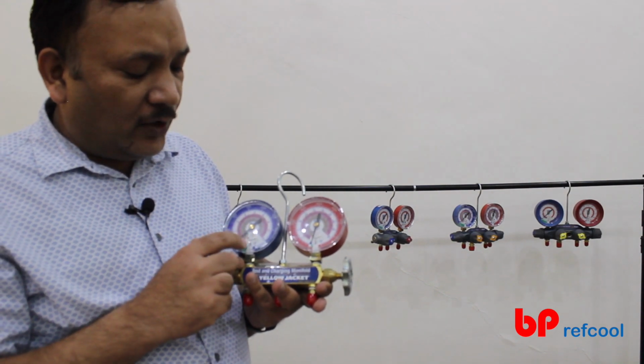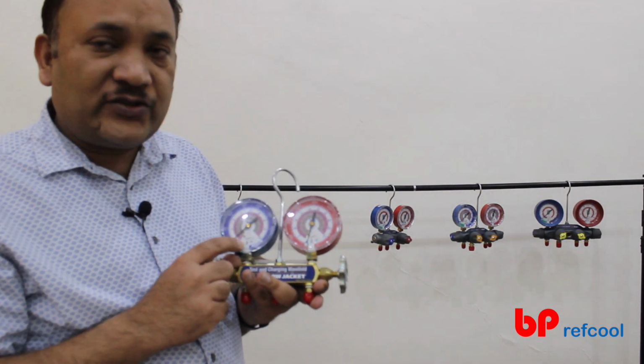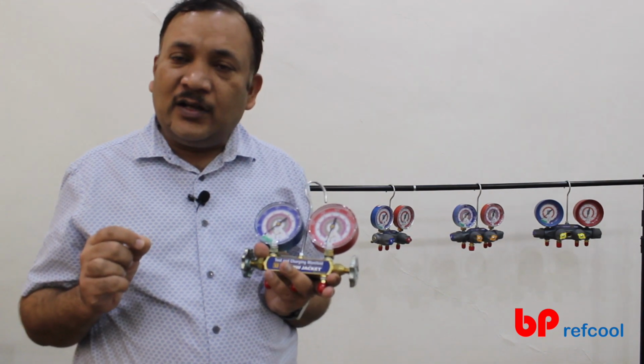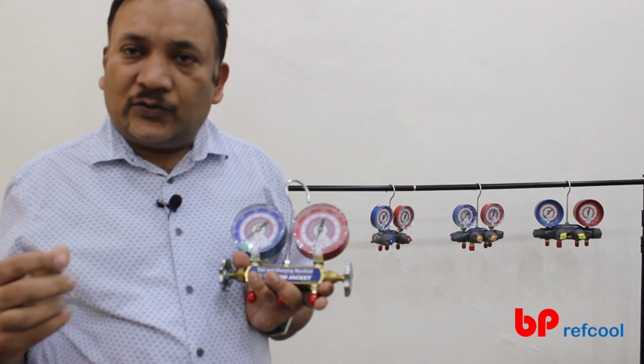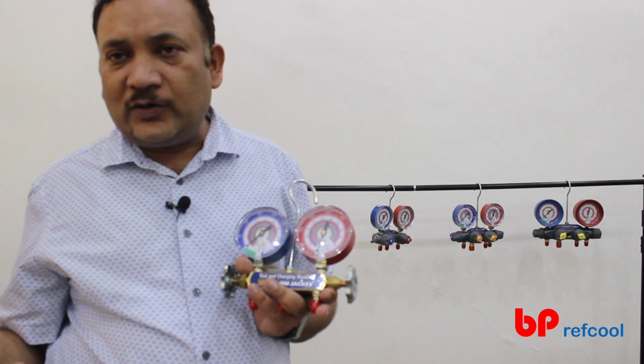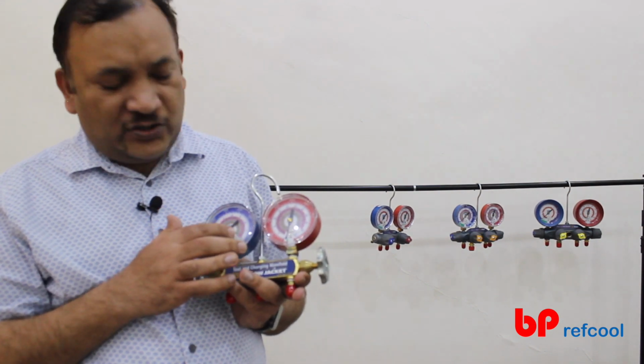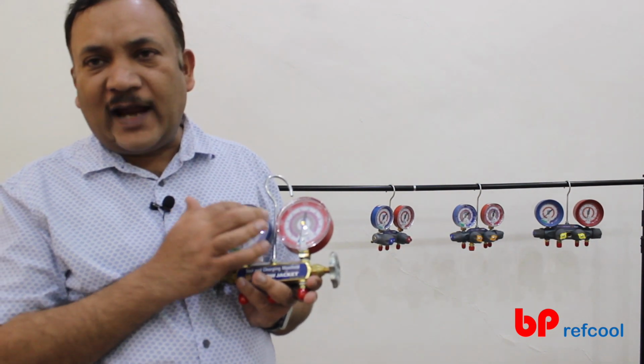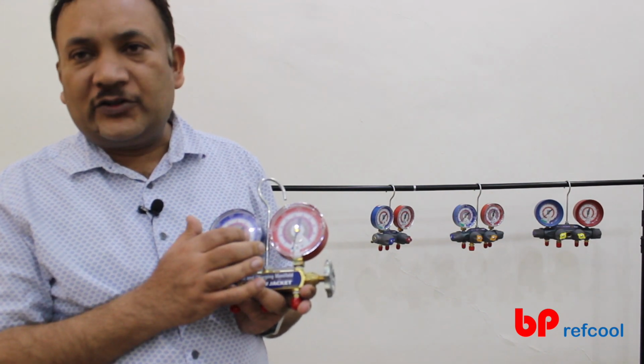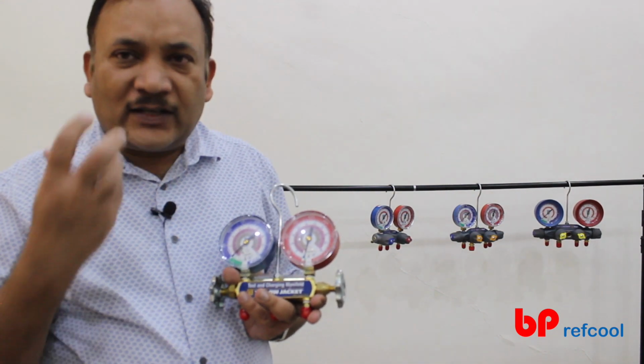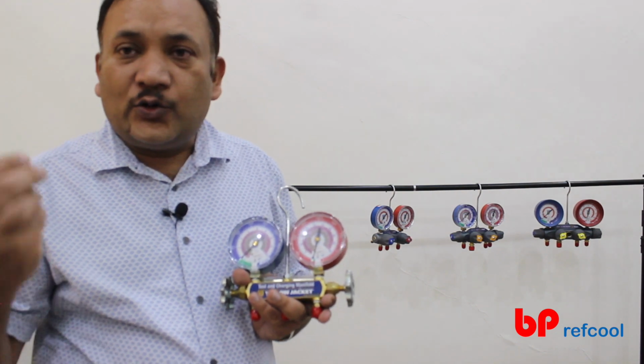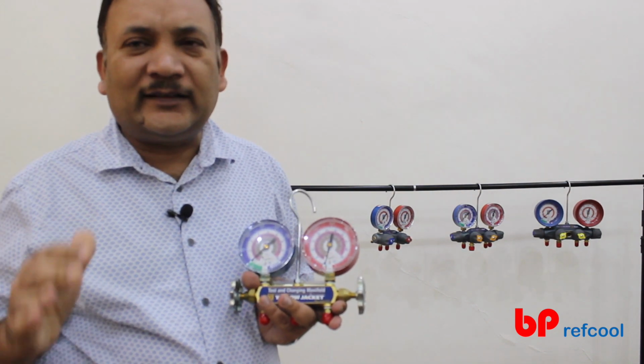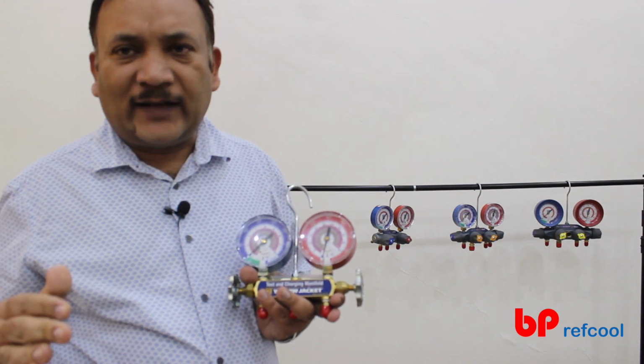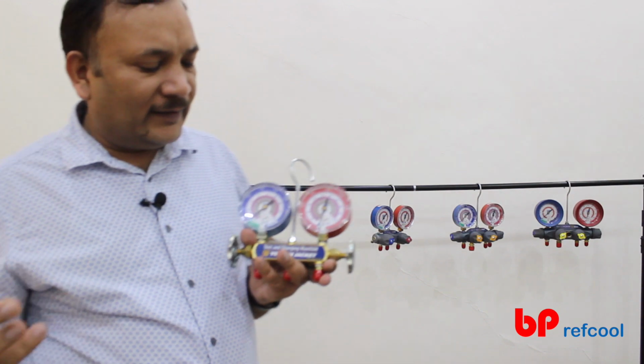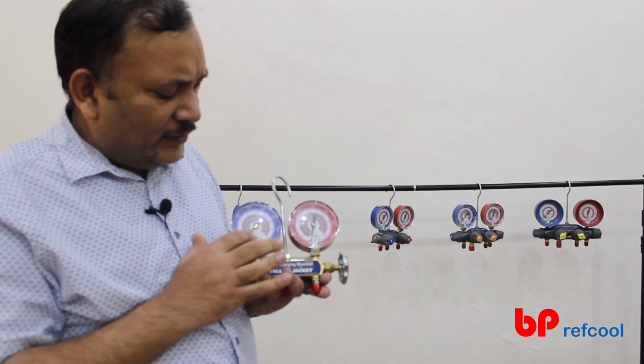The significance of the refrigerants available on the gauge is to give you a calculation for superheat and subcool. If you are not going to use a superheat or subcool calculation, then honestly you will just be looking at pressure, not temperature. The temperature gives you the saturation temperature of that refrigerant to calculate the superheat, and superheat is very important for us as refrigeration and air conditioning engineers to know for any kind of system.